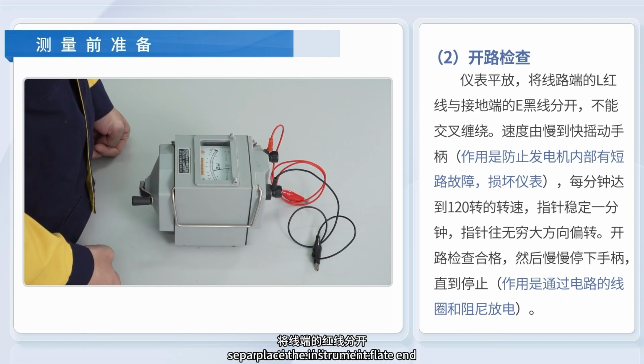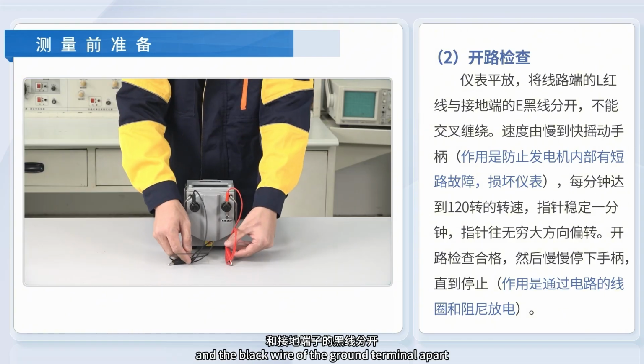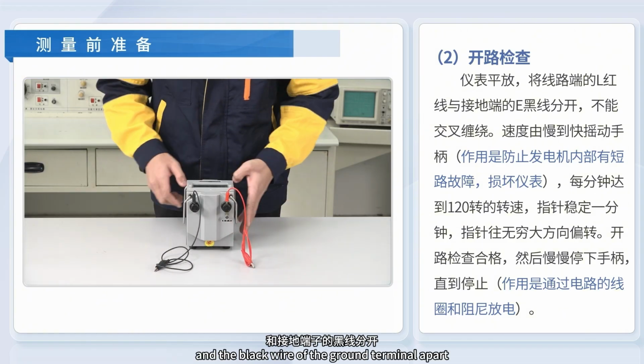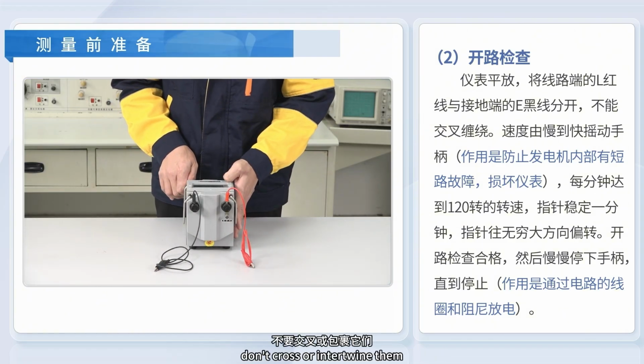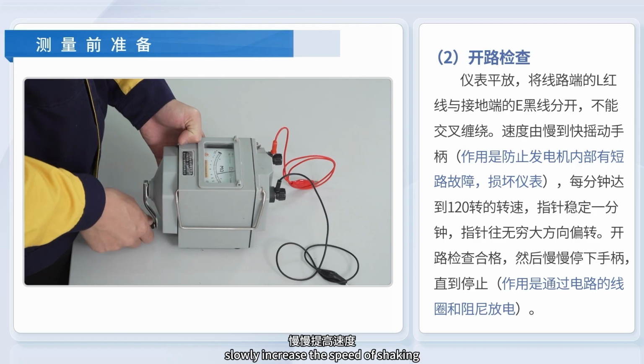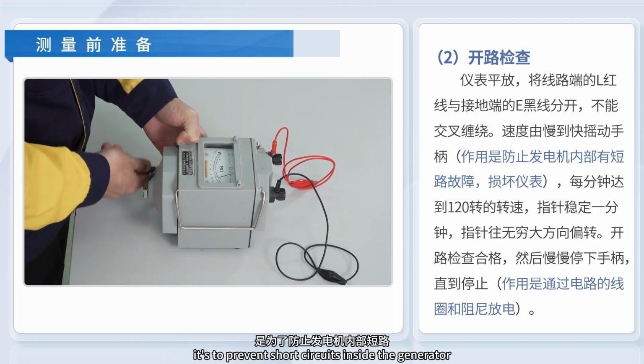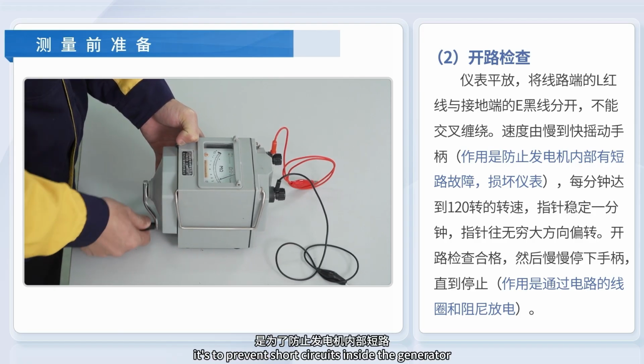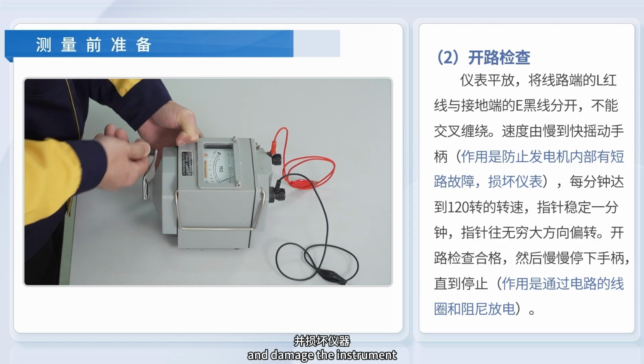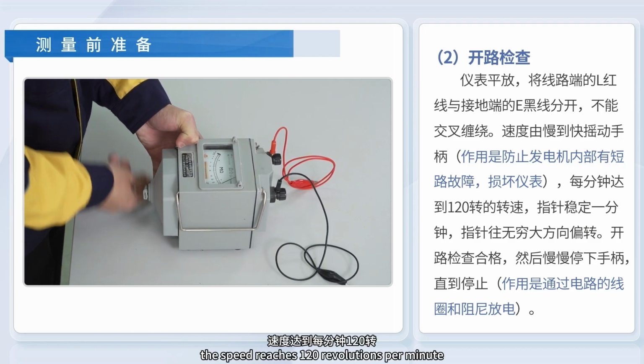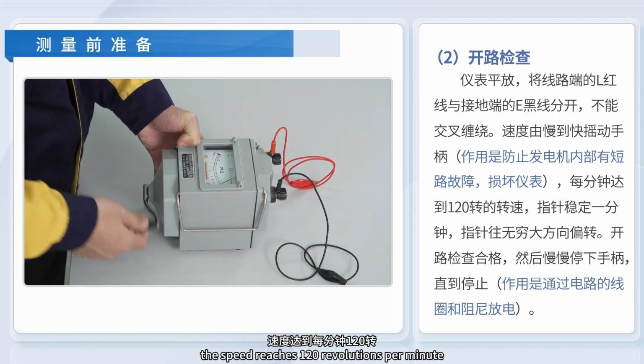Place the instrument flat. Separate the red line at the line end and the black wire of the ground terminal apart. Don't cross or intertwine them. Slowly increase the speed of shaking. Shake the handle slowly to prevent short circuits inside the generator and damage to the instrument. The speed reaches 120 revolutions per minute.